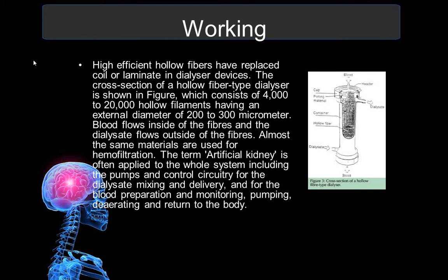The term artificial kidney is often applied to the whole system, including the pumps and the control circuitry for the dialysate mixing and delivery, and for the blood preparation and monitoring, pumping, deaerating, and return to the body.